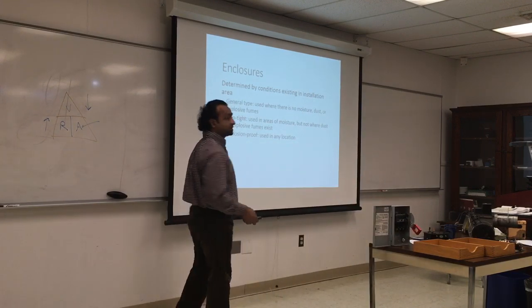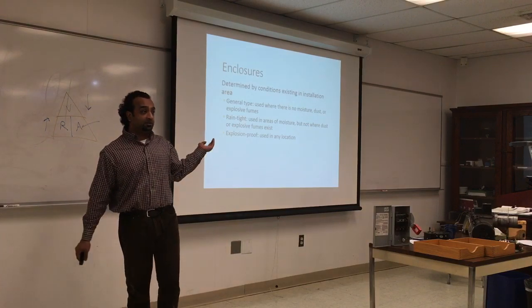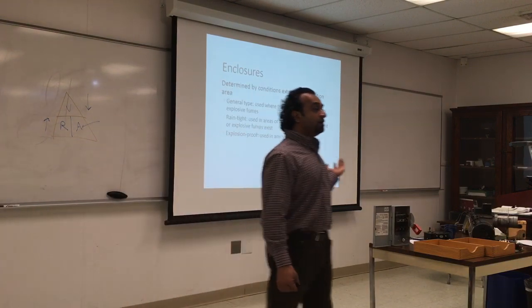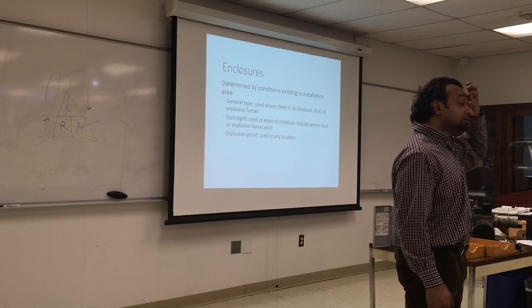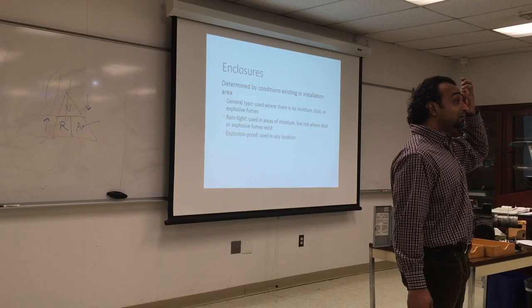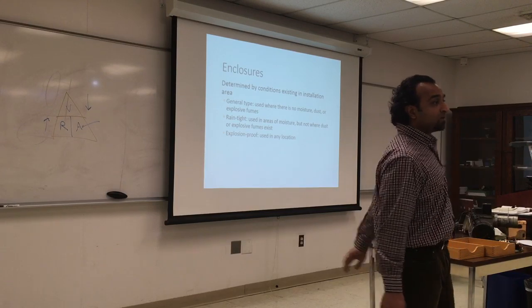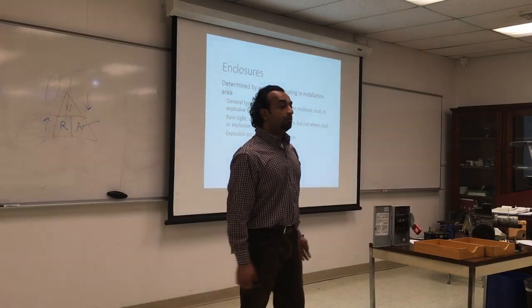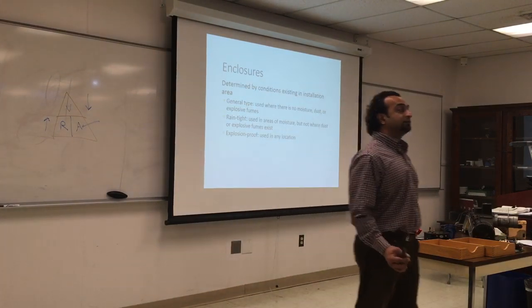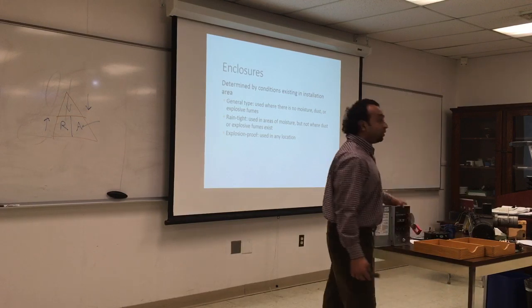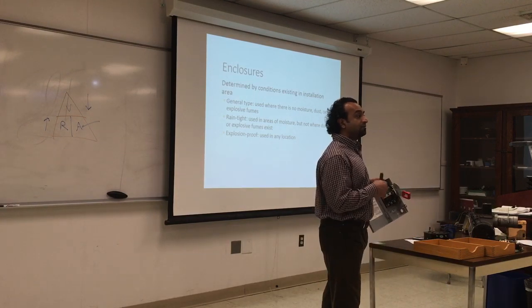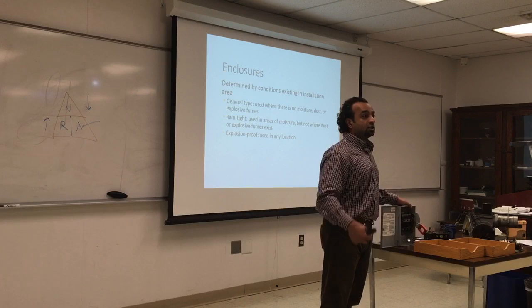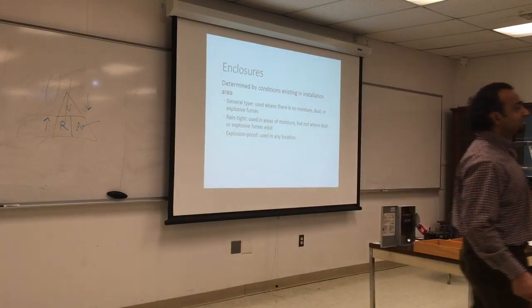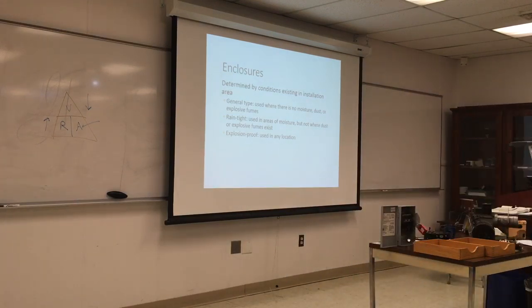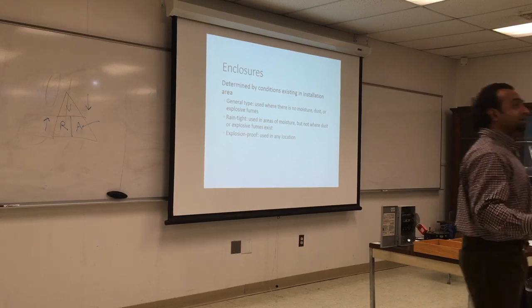Explosion proof. These, of course, can be used anywhere, but they're a little bit more expensive. Where would you find explosion proof boxes and enclosures? Power plants, yes. Power plants, refineries, places where they have a lot of gas and there's a possibility of an explosion. You want all the enclosures coming from the disconnect switch to the equipment to be explosion proof. Why? So in case there is a small explosion or even a big explosion, it would not tear away all the wires and disconnect and exacerbate the problem.